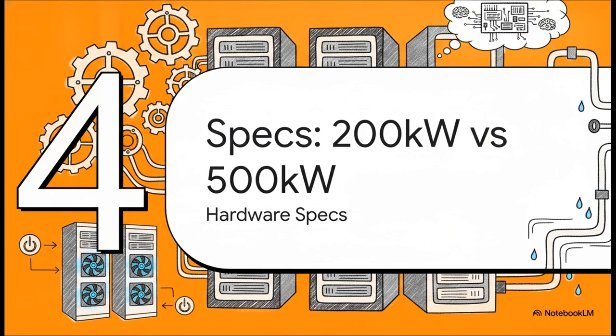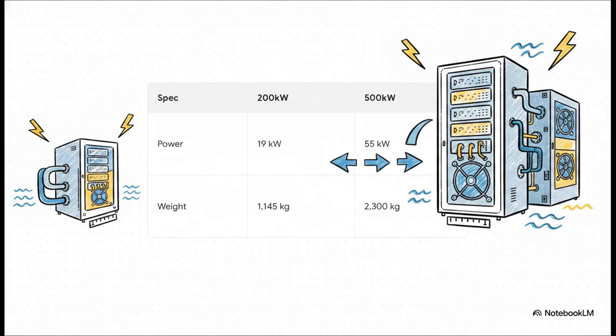All right, let's talk hardware in Section 4: specs, 200 kilowatt versus 500 kilowatt. For the IT pros and facility engineers tuning in, let's put these two main models side by side. First up, we've got the 200 kilowatt cooling capacity model. Its maximum power consumption to run the sidecar is 19 kilowatts, and it weighs in at a pretty hefty 1,145 kilograms. And mind you, that's before you even add the coolant.